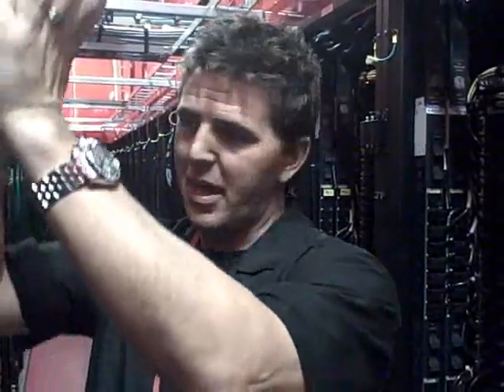The heat starts to move over into the cold aisle, and then once these server fans catch that heat and pull it through the device, the thermal mass of the device gets a little hotter, so then it's putting more heat out. Here, that never happens. You have 68 degree air keeping them at the most efficient temperatures they've ever read this gear at, of any site they have it in.